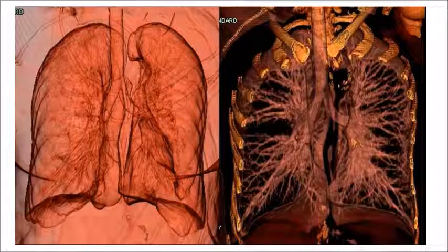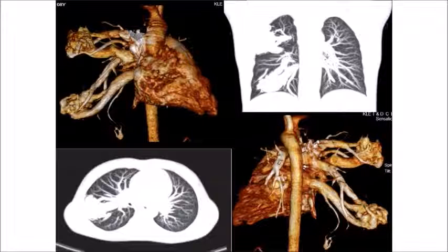For example, the bones of the pelvis could be displayed as semi-transparent so that even at an oblique angle, one part of the image does not conceal the other. A threshold value of radio density is set by the operator. From this, a three-dimensional model can be constructed using edge detection image processing algorithms and displayed on the screen. Multiple models can be constructed from various thresholds, allowing different colors to represent each anatomical component such as bone, muscle, and cartilage. However, the interior structures of each element is not visible in this mode of operation.